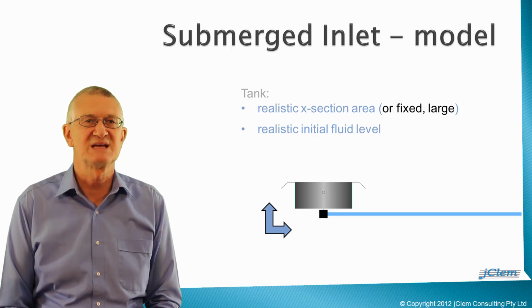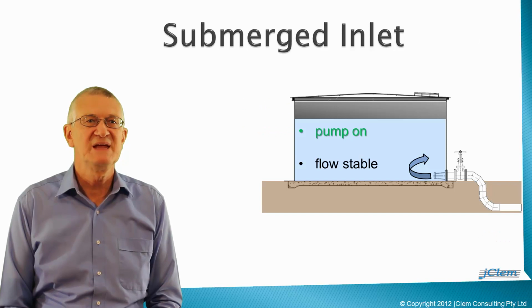Consequently, this lesson presents better approaches to modelling the discharge point on some pipelines, with consideration of the physical pipe arrangement at the discharge point forming the basis for the improved models. When the inlet pipe is submerged, unless there is a non-return valve installed on the inlet pipe, flow in the storage is always accessible for discharge back into the pipeline during transients.